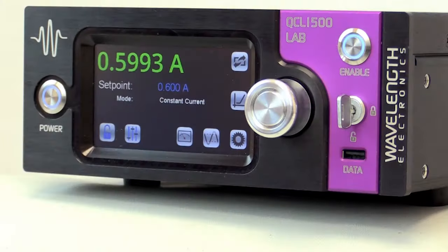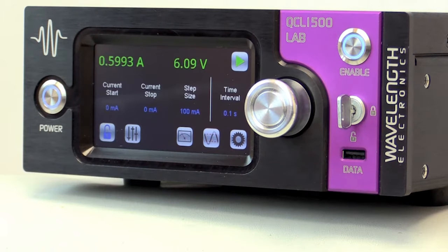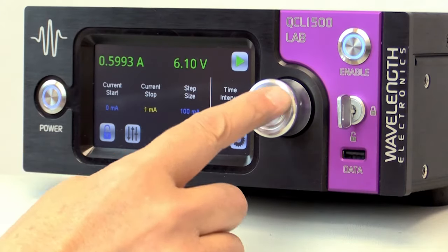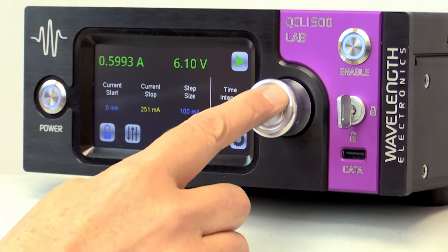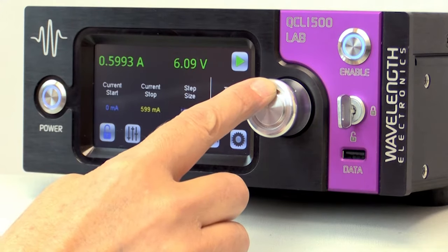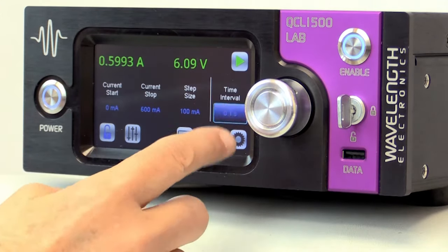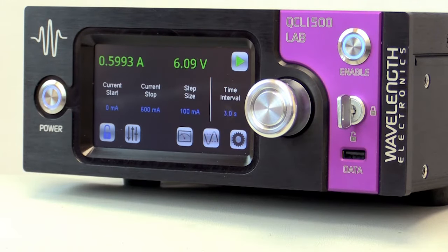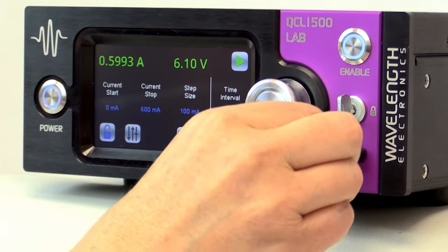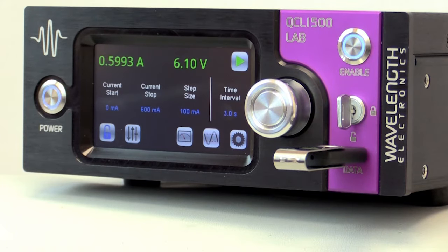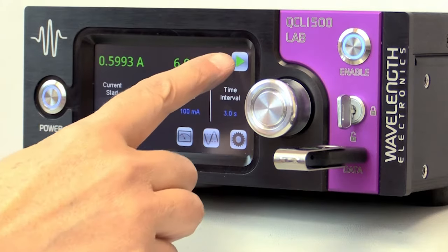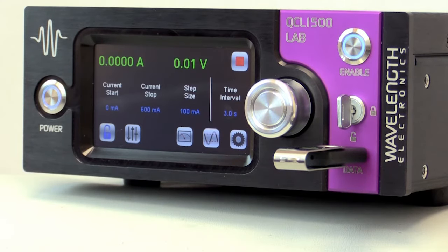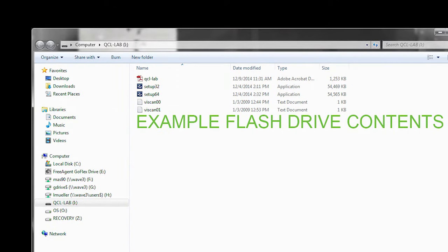On the control screen, press the VI scan icon. Press the blue text under each option and turn the adjustment knob to change each value. We recommend a minimum scan time interval of 3 seconds to achieve the most accurate data. The scan data is saved to a USB flash drive, which must be inserted in the front panel before starting the scan. To start the scan, press the run icon. Any data collected during the scan is automatically saved to the flash drive, whether the full scan was completed or stopped mid-scan.